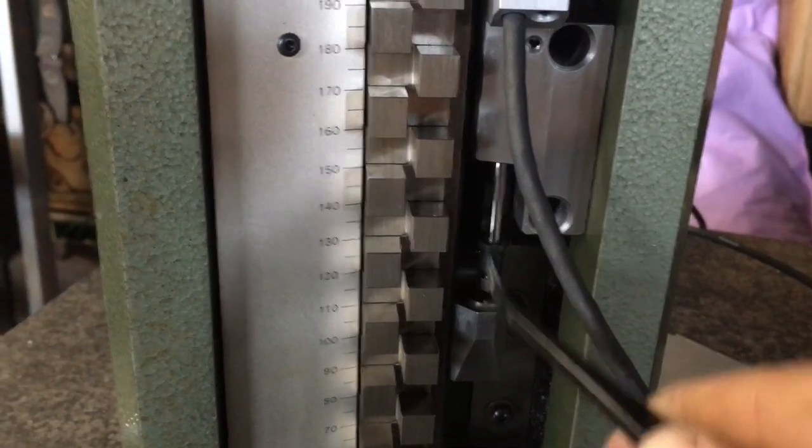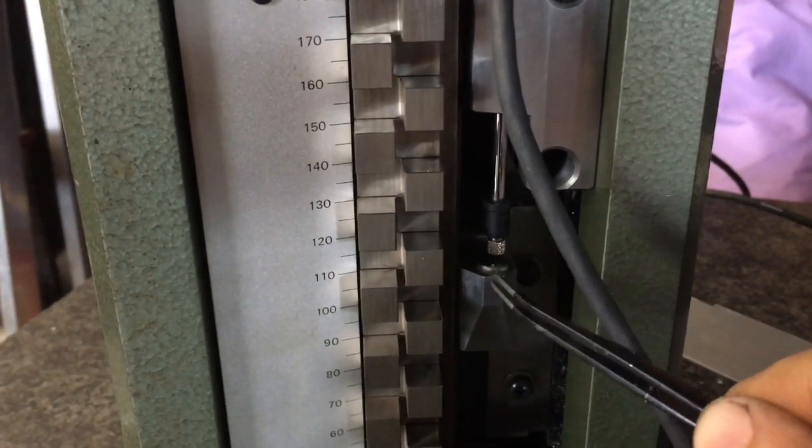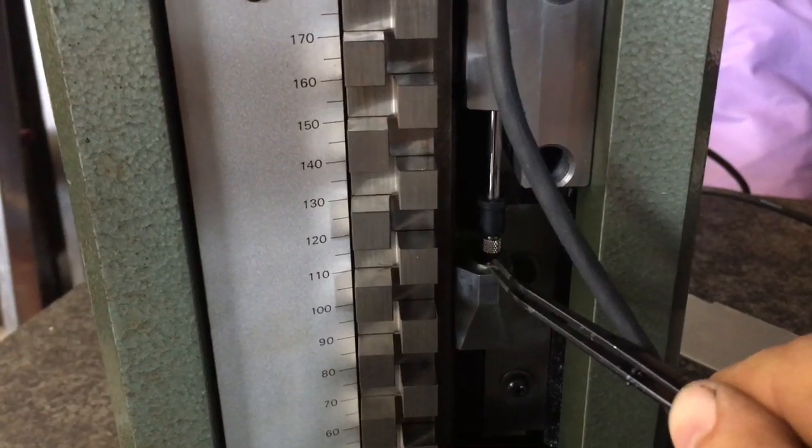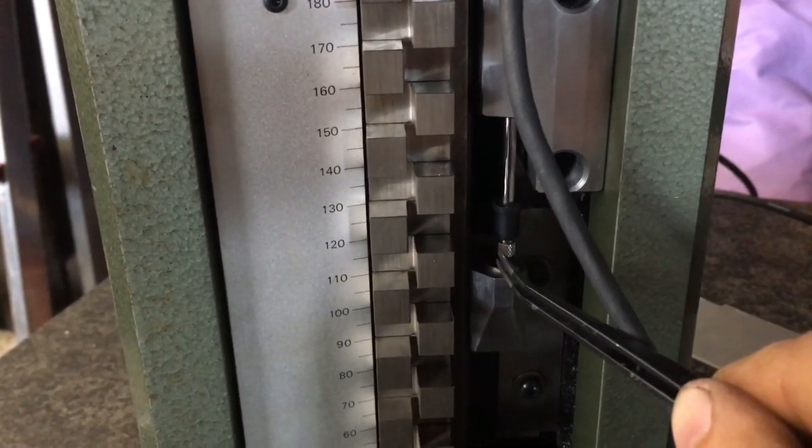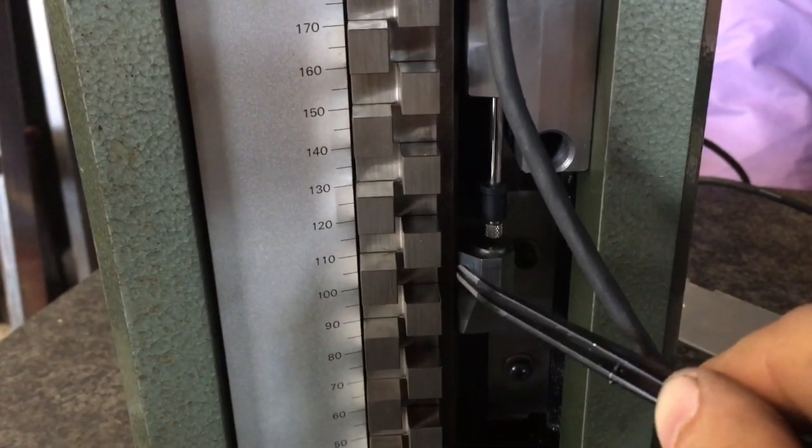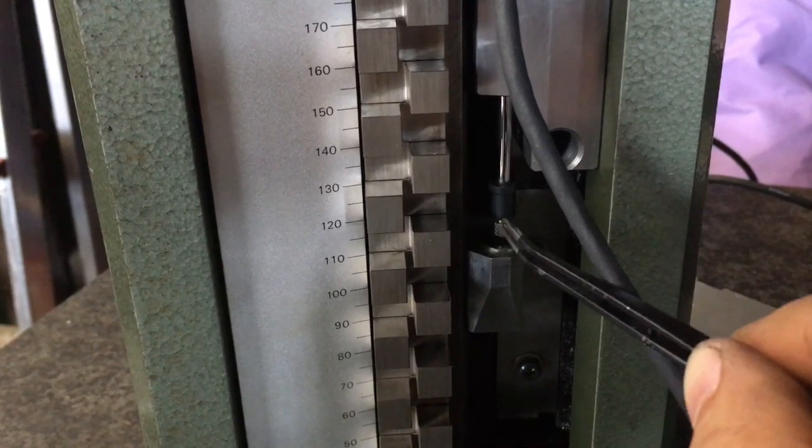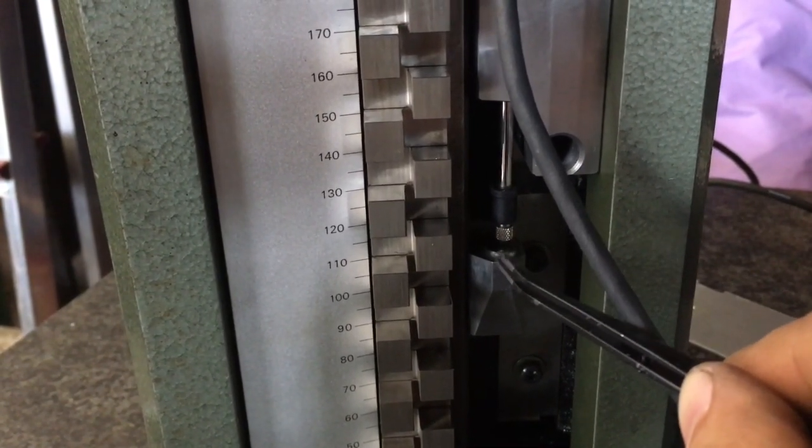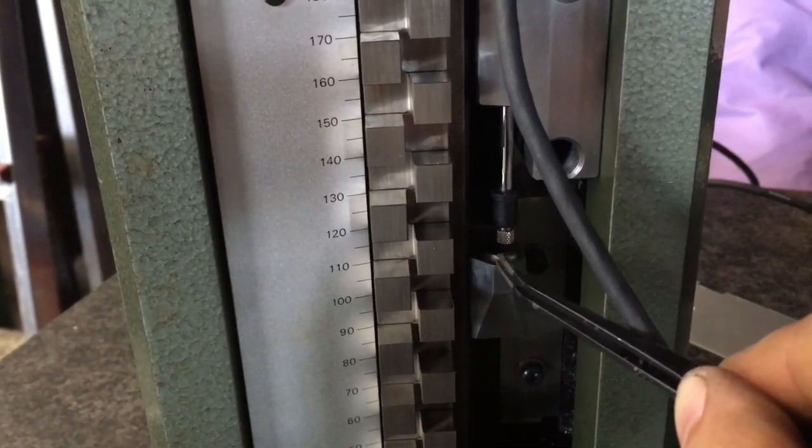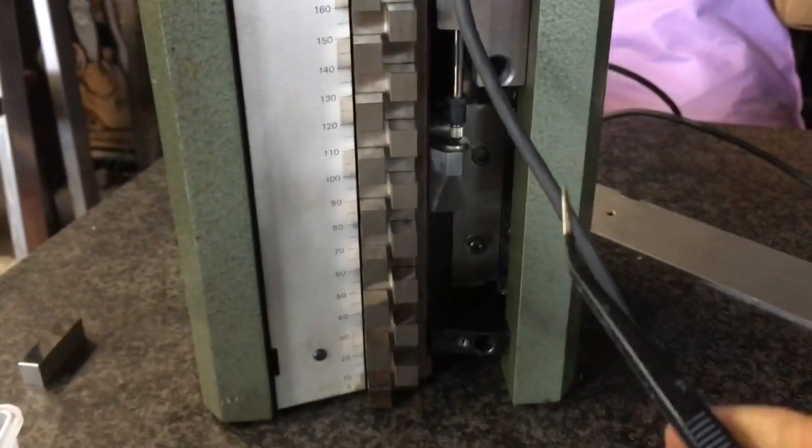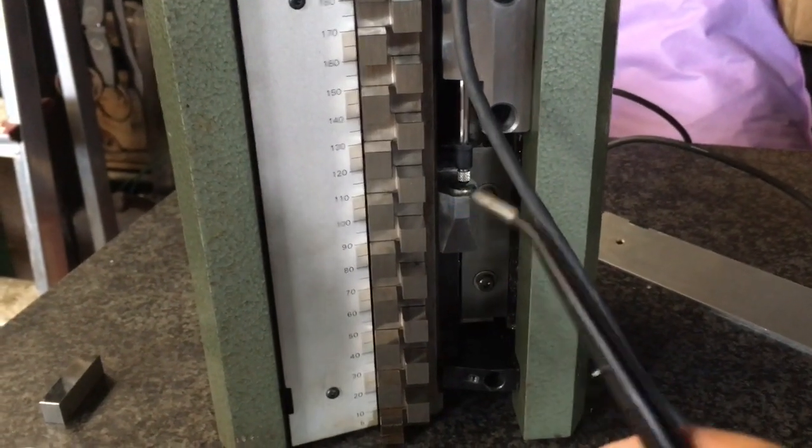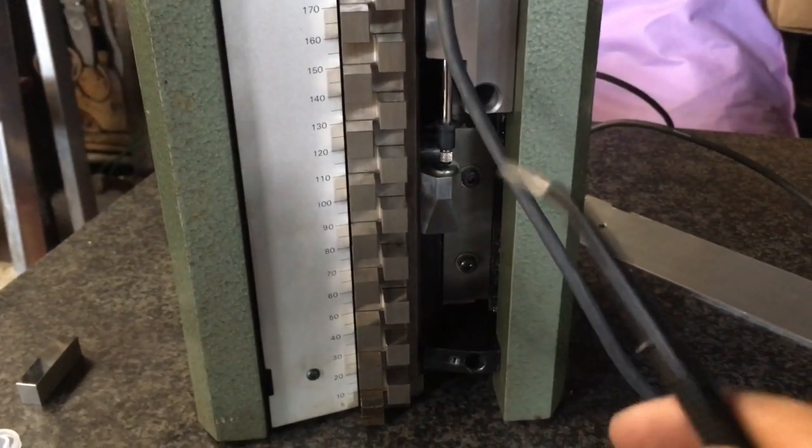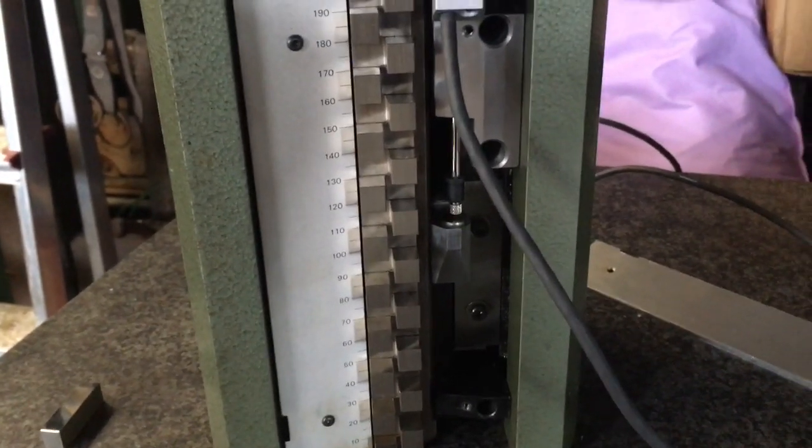When the stem goes up and down, if this and this is on a bit of an angle, if this wasn't perfectly aligned with the axis of motion, then you have a small actual displacement adding up because it's kind of running on an angle. This may be a little bit OCD, but I prefer to remove all those tiny little errors to make it as efficient as I can.